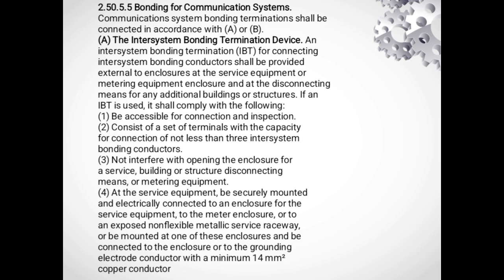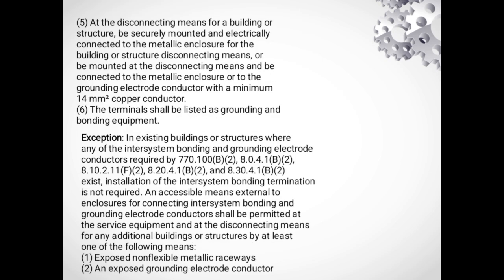Section 2.50.5.5 addresses the bonding of communication systems. Letter A introduces the inter-system bonding termination, or IBT, device. The IBT provides a central termination point for bonding communication system grounding conductors to the building's grounding electrode system. This minimizes potential differences between the power and communication systems. Number 5. At the disconnecting means for a building or structure, be securely mounted and electrically connected to the metallic enclosure for the building or structure disconnecting means, or be mounted at the disconnecting means and be connected to the metallic enclosure or to the grounding electrode conductor with a minimum 14 mm squared copper conductor.